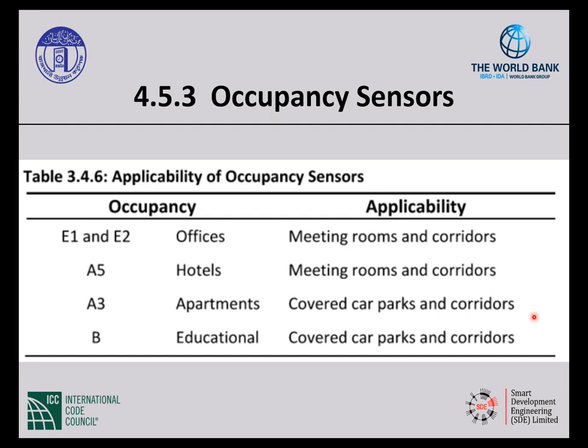I love this code so much because it tells you not just what the requirement is, but why. In order to limit the use of electricity in the unoccupied areas of the building that are linked to the lighting, we're going to provide these sensors. That's nice to know that that's why they want you to do it, not just because. So it does go on to say that if you have car parks, so in your apartments and your educational where you're required to put your occupancy sensors, a minimum of 2/3 of the lighting has to be controlled by occupancy sensors. And then it goes further to just say that the emergency lighting cannot be on occupancy sensors in any of the buildings.